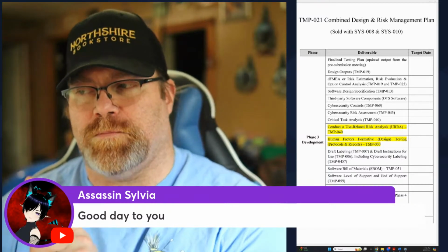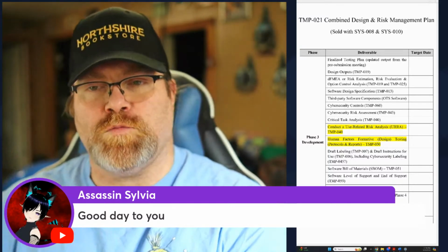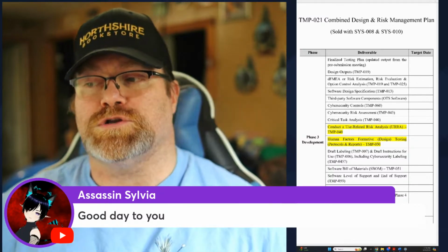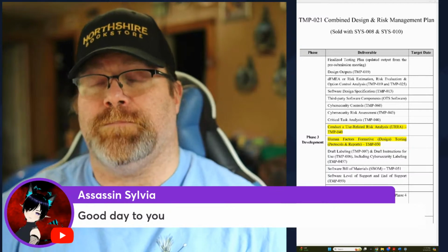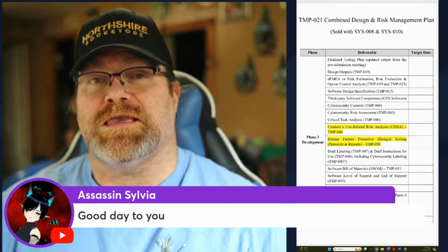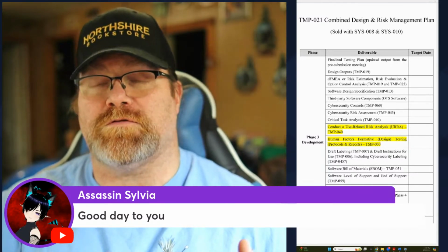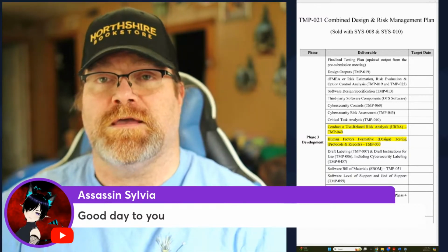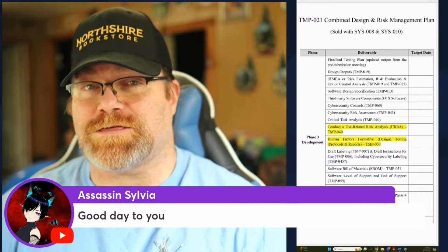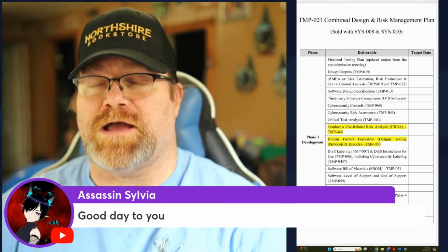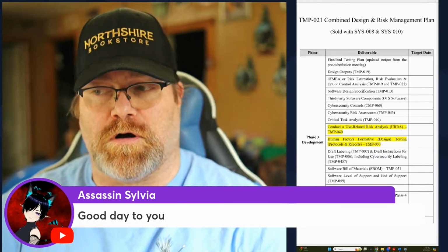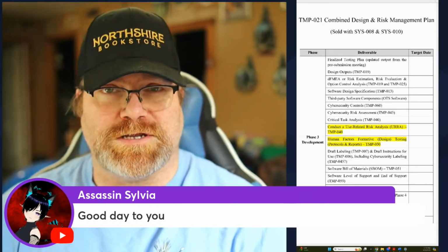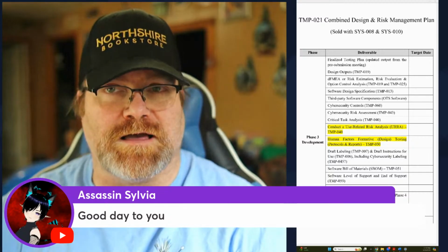why. And to repeat it one more time, the reason why you would do a URRA before you're going to do the formative testing and before you're going to do your summative testing is because you have to identify what tasks are critical. You're going to use that URRA to create a draft summative protocol, and you might be executing that draft usability protocol as a dry run for formative testing. You might be doing it with some volunteers in your company, some people that are existing customers.